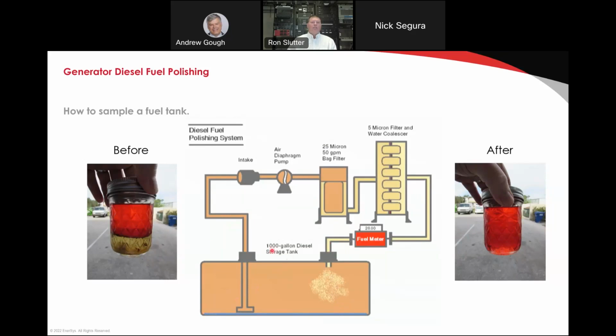Now, what you see here is an input and an output, right? Not every tank has two fittings. Some of them only have one fitting. If you have one fitting in your tank, and it's a small tank, you can probably still perform this fairly well. Hopefully you're mixing it up enough. What you don't see here, that is true for almost every sub-base fuel tank, is there are baffles in this tank, and they are almost complete. Every 2 feet, there's usually a large steel plate from top to bottom. How they let the fuel transition between those plates is they cut the corner off when they weld the plate in.